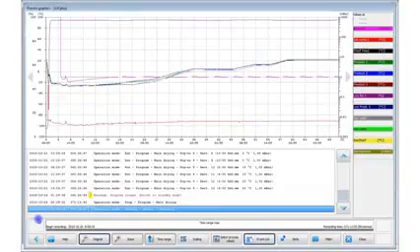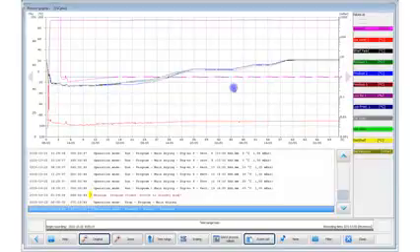The documentation window shows a list of all process records. You can use the filter function to search for specific processes based on the batch data stored in the record. A list of processes matching your search criteria is displayed. After you have selected a process, the process graphics and the associated process events list are displayed. Now you can analyze the process history in detail. For example, you can see when it switched to main drying mode. Also, any messages or alarms that were generated, or pressure and temperature curves during the process, can be found in the process events list.